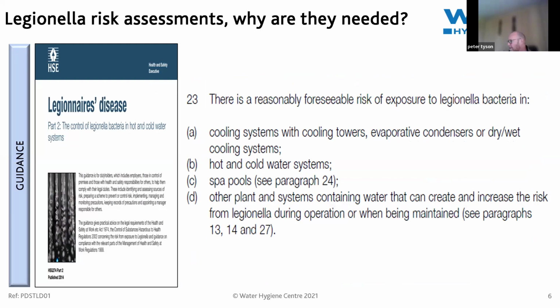It does state that there are 4 areas: cooling systems with cooling towers, evaporative condensers or dry wet cooling systems; hot and cold water systems; spa pools; and other plant and systems containing water that can create and increase the risk from Legionella during operation or maintenance. That last part is a fantastic CYA, meaning basically everything and anything else where water surface tension is broken and an aerosol can be produced, therefore it has an inherent risk of being a contaminated aerosol that can be breathed in, which could contain Legionella bacteria. Does that make sense?